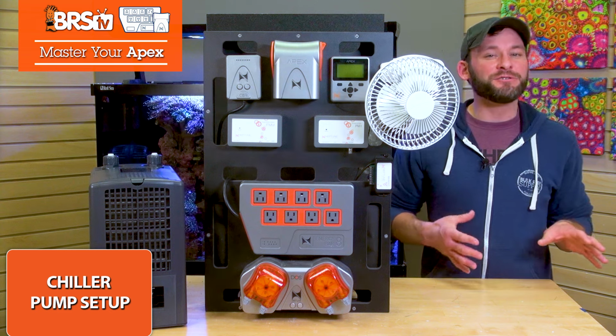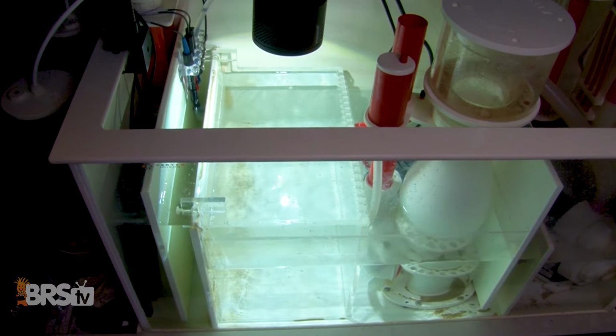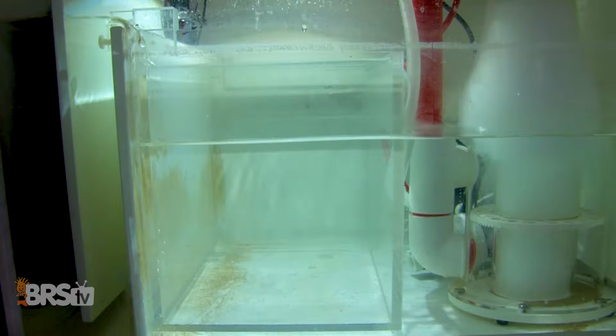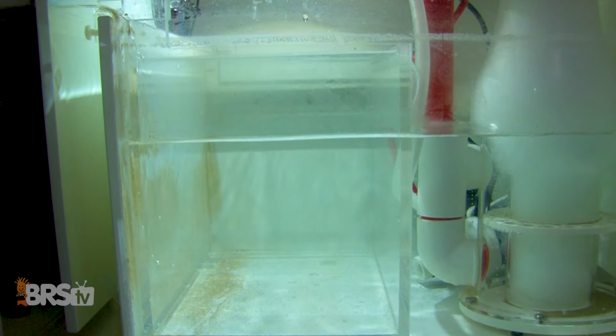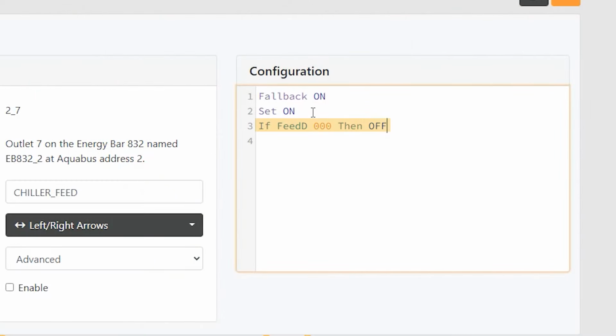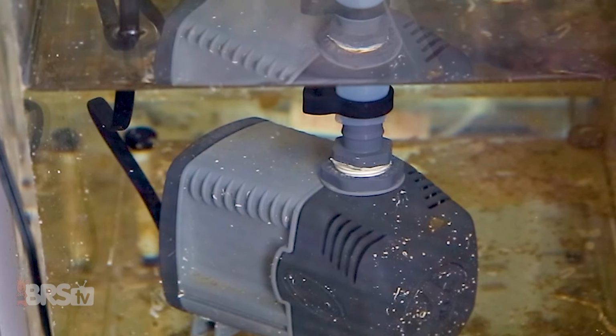Along with that, if you're like me and use a feed mode for deep tank maintenance like cleaning out the sump periodically, and you don't want your chiller pump to be on, you can add in a line that says if feed D000 then off, which will keep the pump off until you're done cleaning.